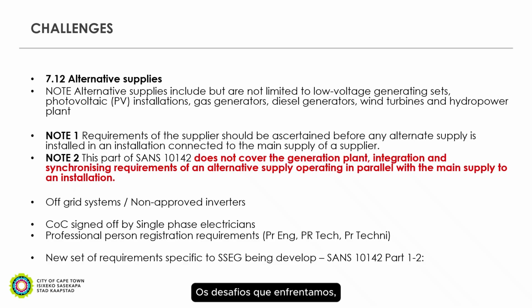The challenges we're experiencing are particularly on the LV side. We've got this South African National Standard document, SANS 10142-1, as we refer to it, where in this particular section 1.7.12 we have what we refer to as alternative supplies. So this standard allows alternative supplies, which includes PV installations. However, it does have a note, as I've indicated in red, where this document does not cover the generation plant, the integration, and synchronizing requirements of the alternative supply operating in parallel with the main supply.